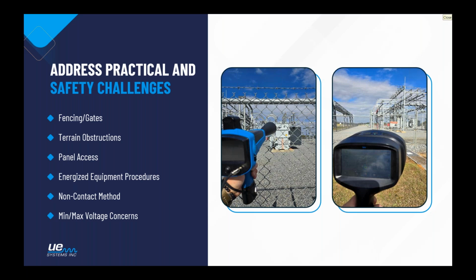And just as with fencing, gating, terrain obstruction, so outdoor power lines in the middle of nowhere, it's a lot easier to inspect them from a great distance. Really, we have the ability to go up to about 500 feet away on different assets and inspect them. So that really helps with some of the obstacles that we would face out in the field. Panel access is another one that we're able to overcome, as long as it is not a solid plate, airtight, watertight. Ultrasound will find a way to escape. So that's where we can listen to the outside of a panel and hear what is going on inside it.